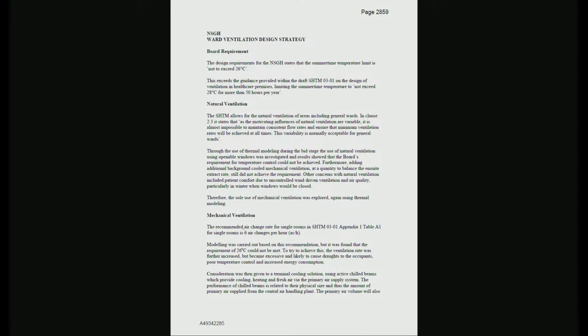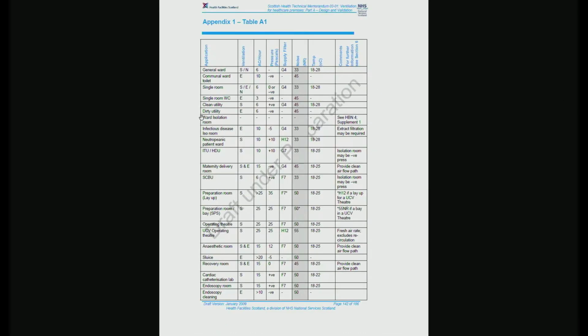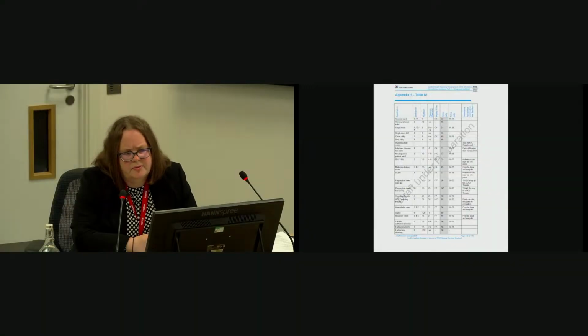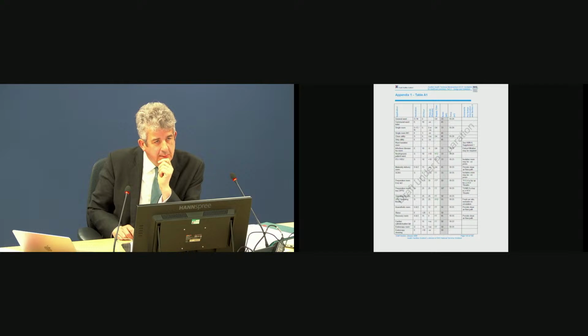Going back to bundle 16, what justification would you expect to see to allow for a lower than 6 air change rate in a general ward? A risk assessment for the patients. My concern is I wouldn't have accepted less than 6 air changes if I'd been involved. Have you ever found out who, in the health board, did accept it? No.